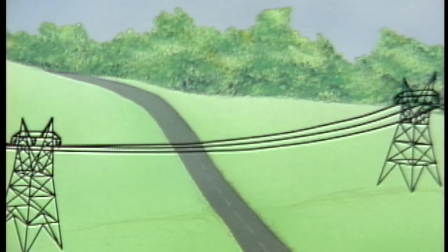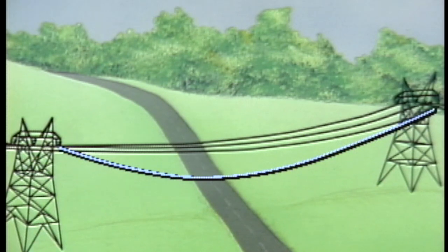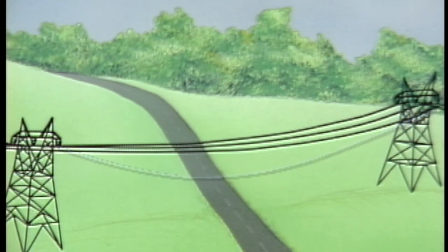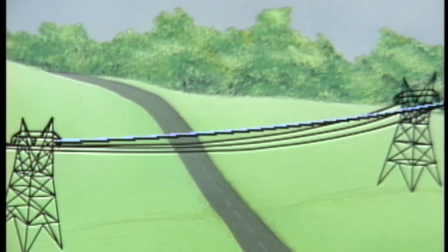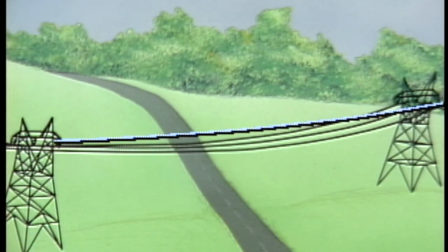Maintaining proper clearances is an important safety and operation concern. Too much sag in a wire could allow wind to cause a conductor to sway into other conductors or a structure, resulting in a fault condition. Too little sag could place excessive strain on structures and conductors, causing them to weaken or break.